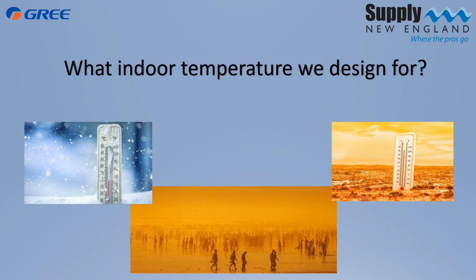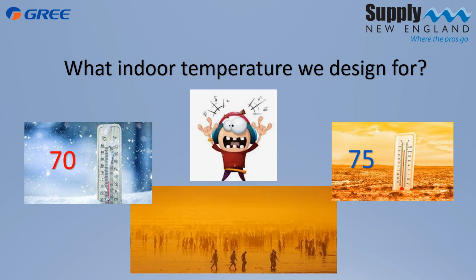Let's start with our indoor design temperatures. In the wintertime, we design to a 70-degree indoor temperature. In the summertime, 75-degree indoor temperature. Sometimes your homeowners go, nope, not going to happen. I want it warmer in the wintertime and cooler in the summertime. But by code, guys, we're not allowed to do that. So what we really need to do is control the humidity, and that's how we're going to keep them comfortable at 75 degrees. If we can get 75 degrees and 50% humidity, they're going to be more comfortable than at 68 degrees and kind of cold and clammy. So let's make sure we're controlling the humidity.